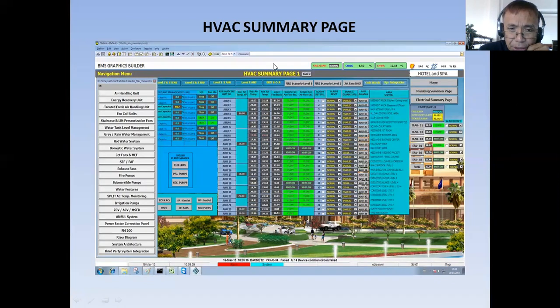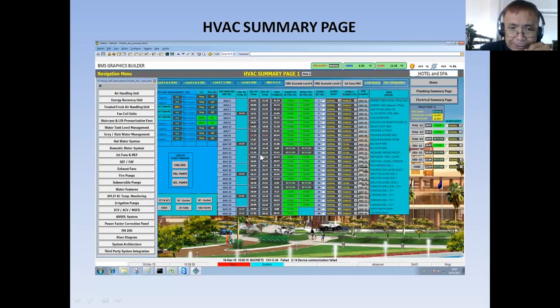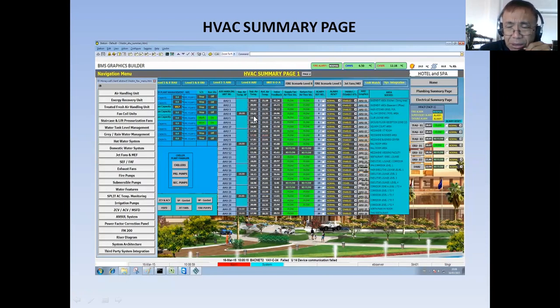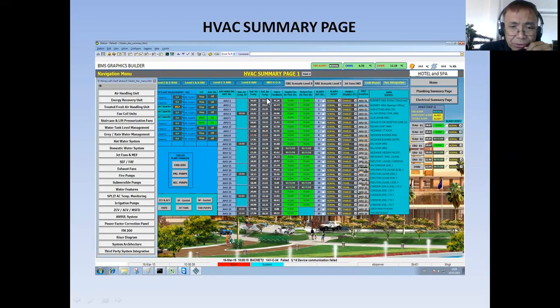I'm displaying the supply air temperature. In one glance, I will be able to know if my AHUs are working properly because you will be able to see the supply air temperature. By just looking at it, you will know that your air handling unit is providing cooling in the area that it is serving. I also have the return air temperature and the valve feedback. With these three pieces of information, you will be able to analyze if your air handling unit is working properly.